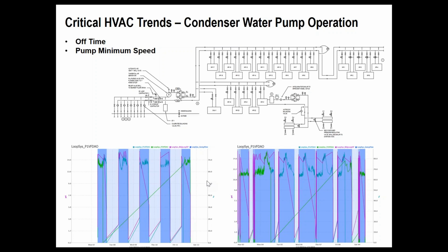Interestingly enough, I took a look back at minimum pump speed and what the assumption was in the energy model. It's a little bit hard to see here, but the minimum pump speed in the actual building is close to 65%. It's not down at 20, 25, 30%, like what we had in the energy model. So that was one of the calibration notes for our calibrated energy model. We are actually using a bit more energy here than what the model predicted, and that tells part of the story of why our HVAC system is using more than the prediction.